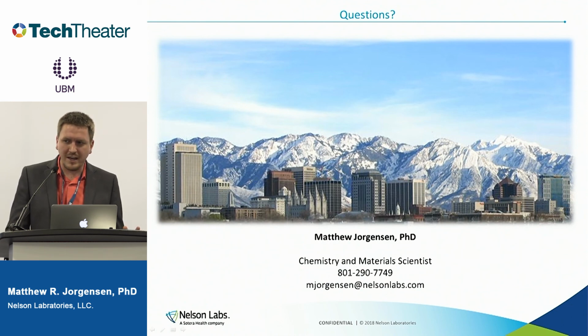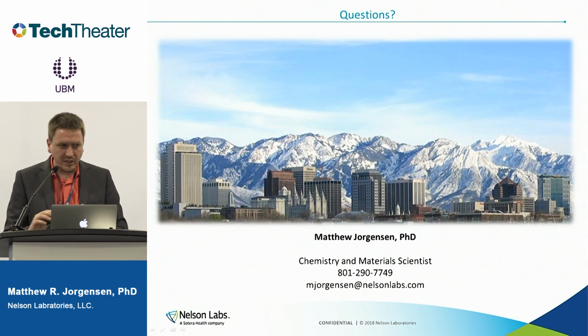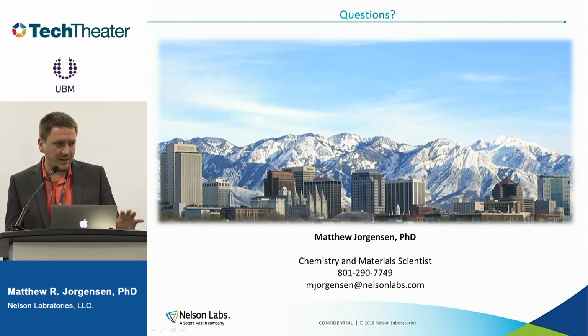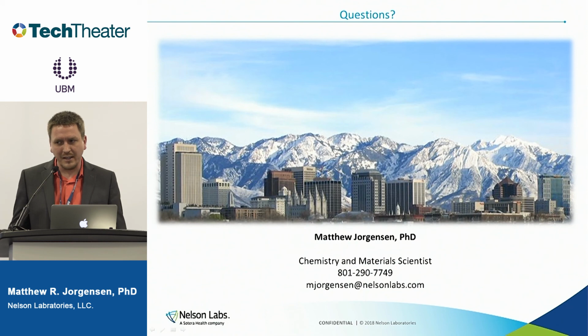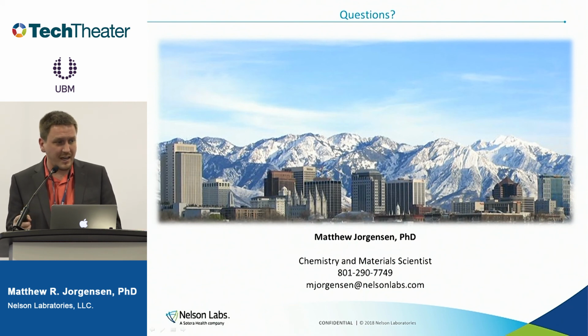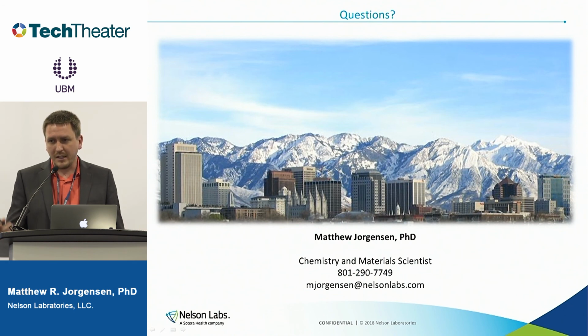I mean that's a great question, and actually I've been getting a lot of requests for packaging testing lately as well. So when it comes to biocompatibility and extractables and leachables chemistry to support the safety of a device, we always want to test on the final finished form of the device, final finished package, sterilized, the whole thing. Where packaging starts to come into play is a couple of places. People might want to test their packaging ahead of that to just screen it to make sure that they're not going to run into a biocomp problem at the very end due to their packaging. And another thing that comes up is that people will go through the entire gamut of biocomp testing for their device and pass everything, and then want to change their packaging. In those cases, they might do something like a packaging comparison test, where they'll test both packages and make sure that there isn't anything new and troublesome coming from the new packaging. But yeah, it's a great comment.